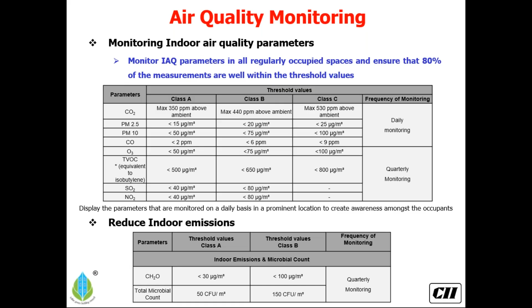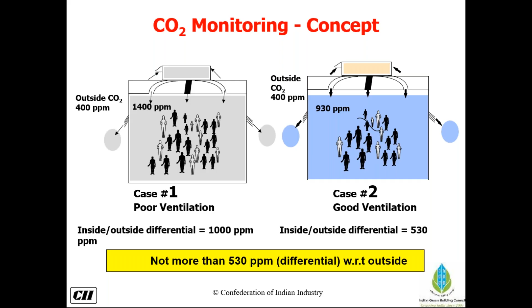Now, to see an example, carbon dioxide monitoring is one of the simplest. We have various instruments available for that. And of course, the standards say that not more than a 530 ppm differential as compared to the outside should be maintained. Anything more than that is not very good air quality. But again, this is segregated by understanding densely occupied spaces and non-densely occupied spaces.